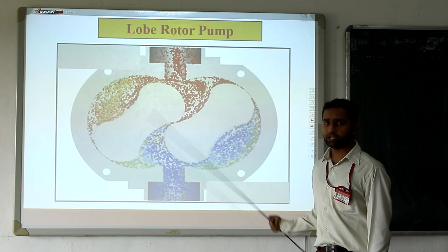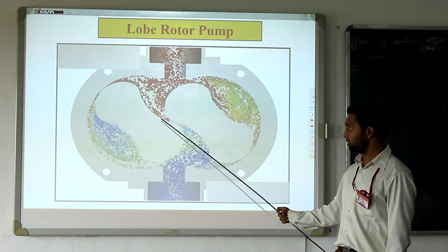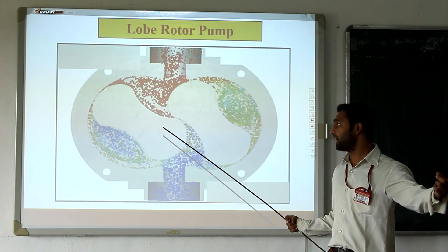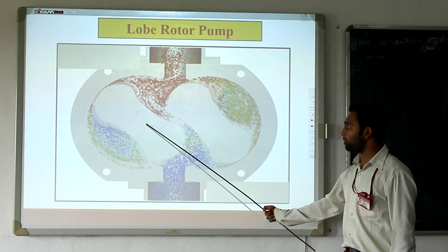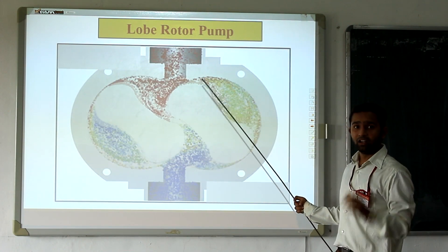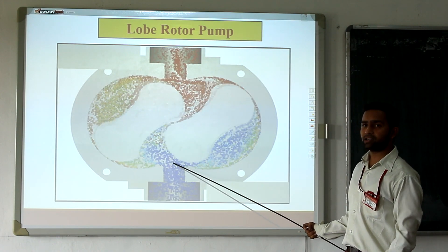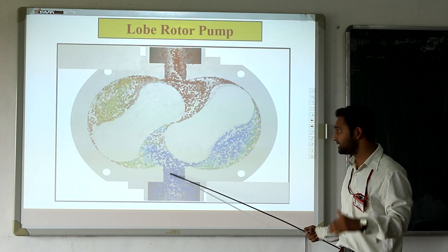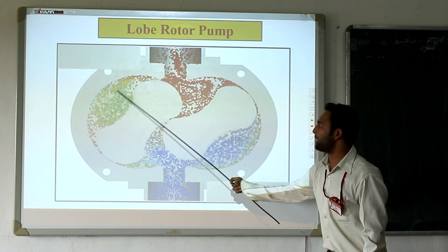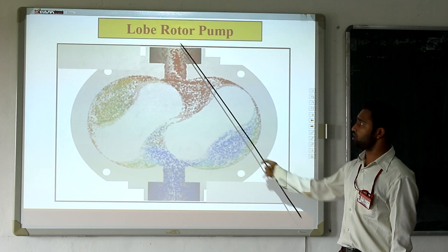Now the lobe pump. The construction of the lobe pump indicates that two lobes are connected with each other but there is clearance at the point. The lobes are mounted inside the casing, and they are driven by external gears mounted outside the casing. In case of the lobe pump, from the downside, suction is possible because area increases, volume increases, pressure decreases, and partial vacuum is created, so suction is possible. Similarly, from the other side, discharge is possible. This is the construction of the lobe pump.